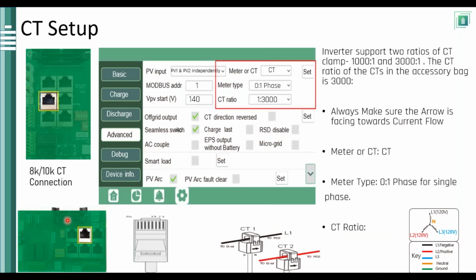So when installing the CT in the designated CT port, what you would do is go to the LCD screen and set up your meter functionality, right? Your meter or CT. You would select CT, and the meter type will be 0-1 phase, and then the CT ratio will be 1 to 3,000, assuming 120/240 split phase solutions, right? Systems will be available for 3-phase around, I would say, beginning of June. So we will have 3-phase applications for these inverters as well, in which case this 0-1 phase would change.